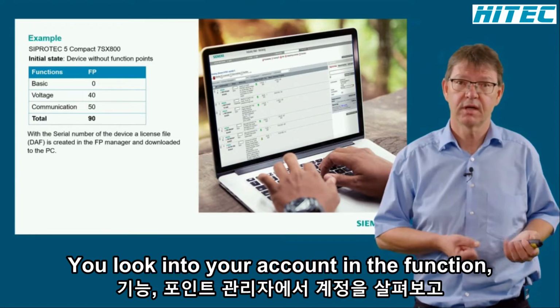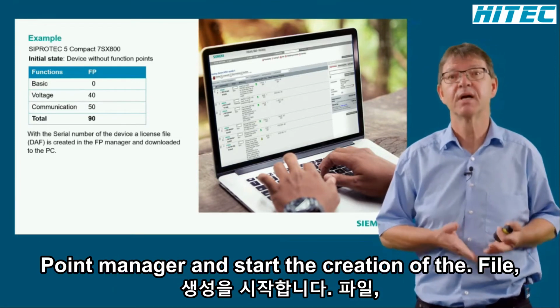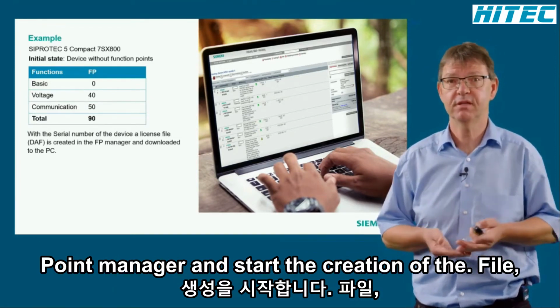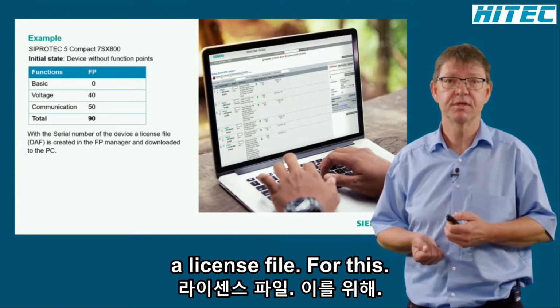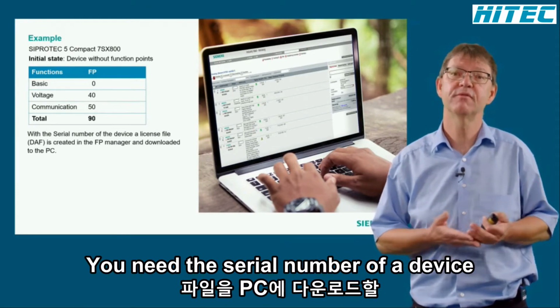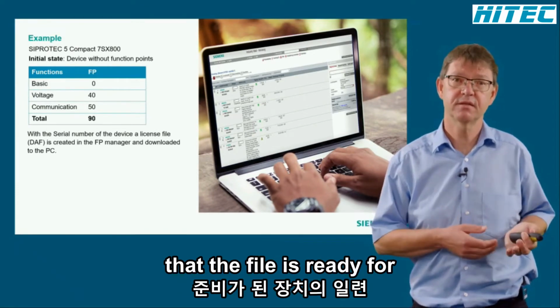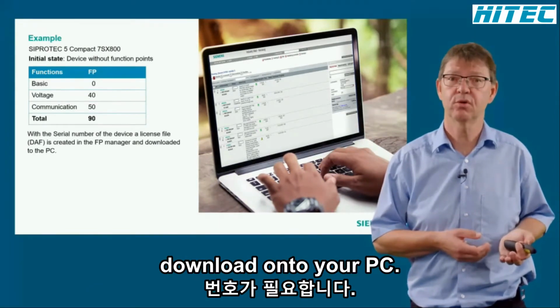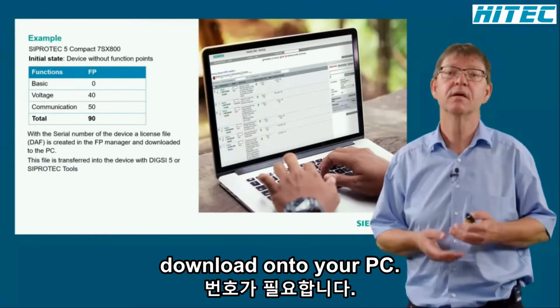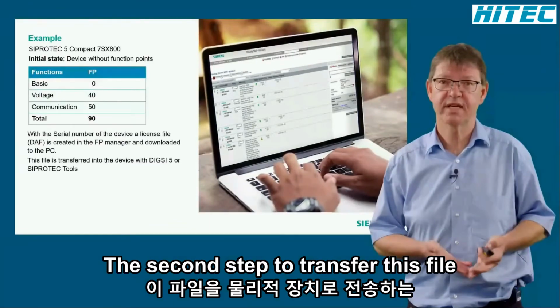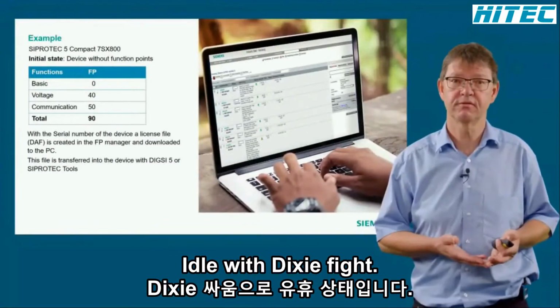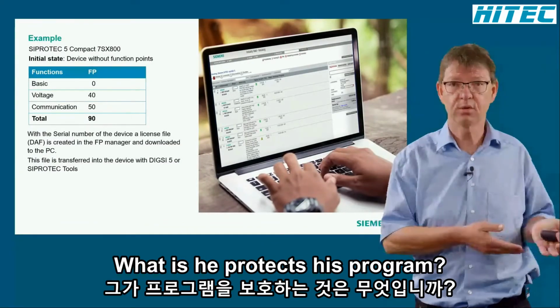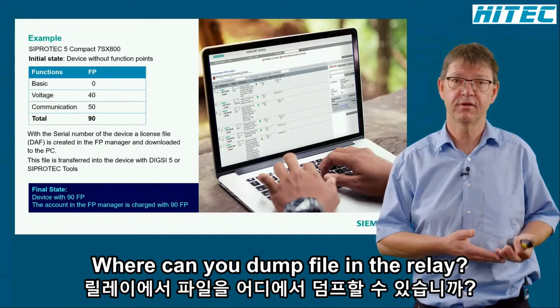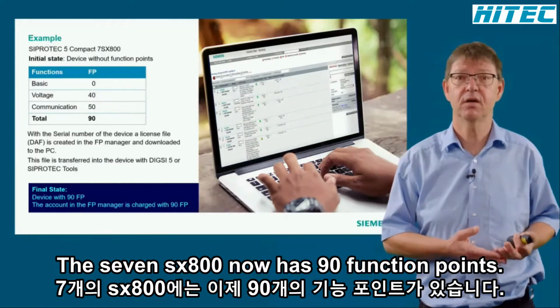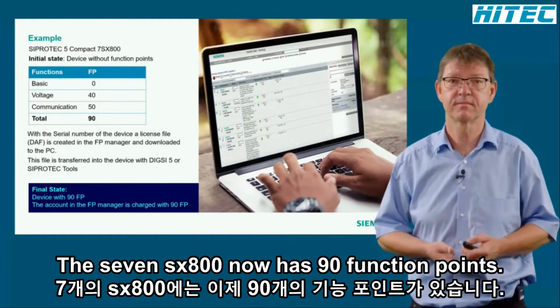You log into your account in the function point manager and start the creation of the DAF file or license file. For this, you need the serial number of your device. After a few seconds, the DAF file is ready for download onto your PC. In the second step, you transfer this file to the physical device, either with DIGSI 5 or the SIPROTEC tools program. With the new DAF file in the relay, the 7SX800 now has 90 function points.